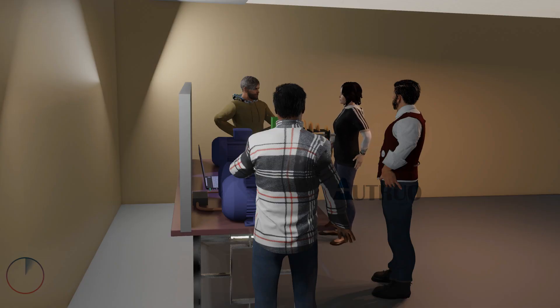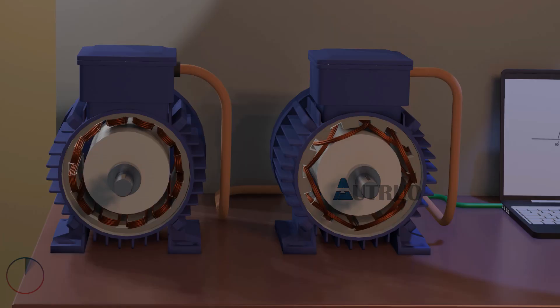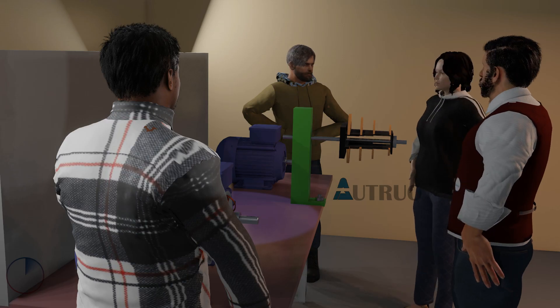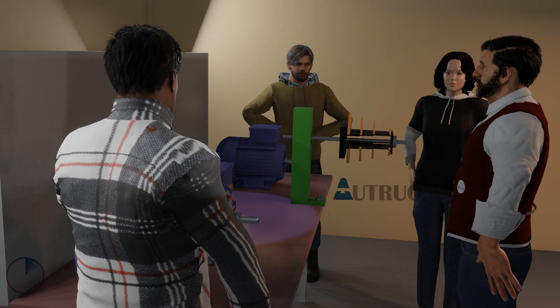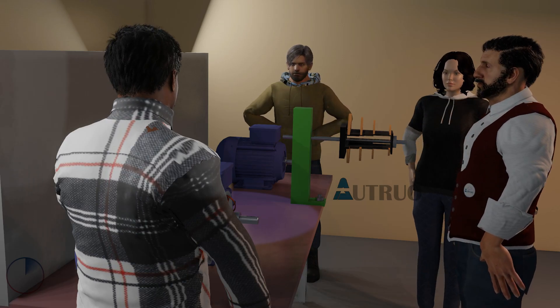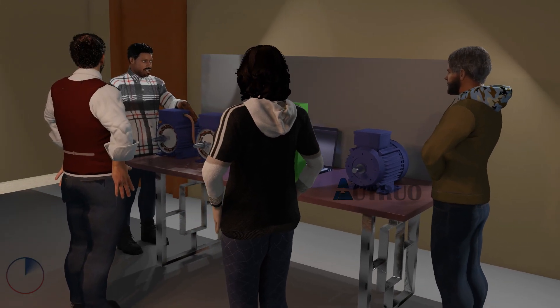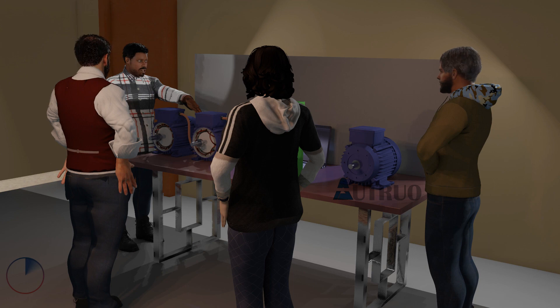By design, in concentrated windings, the coil is usually wound on a single stator tooth. While in distributed windings, the coil is usually wound on two or more stator teeth. Looking at these two motors here, on one hand is a motor with concentrated windings, while on the other hand is a motor with distributed windings.